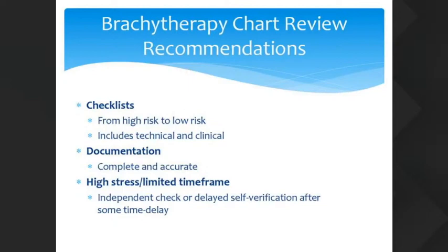And high stress limited time frame, HDR is truly in this category. So we recommended an independent check. And if you can't have it, if you're the same person that planned and checked, then we recommended delayed verification, self-verification after some time delay. Hopefully that's in your practice, where if you're doing the plan, then you take lunch, you come back immediately after lunch, or short break, and you do another verification, a self-verification. It's been proven that this time delay in between the plan and the verification is very helpful.